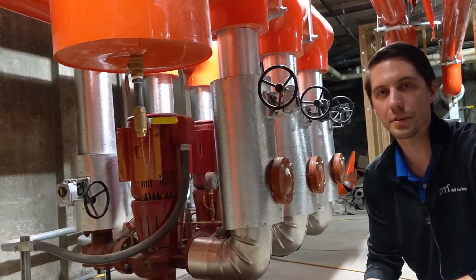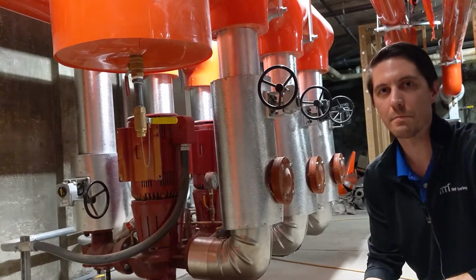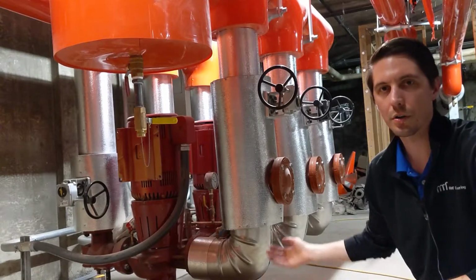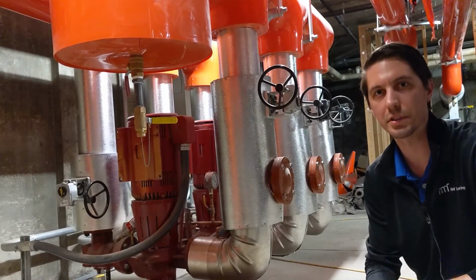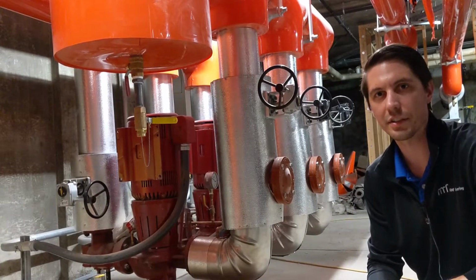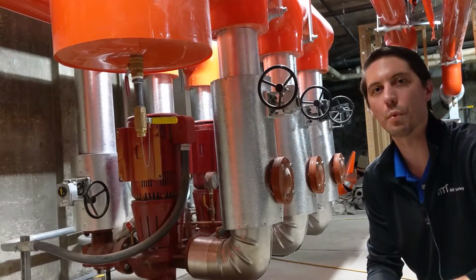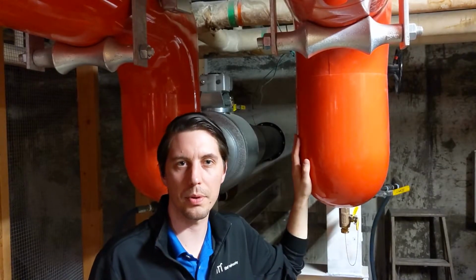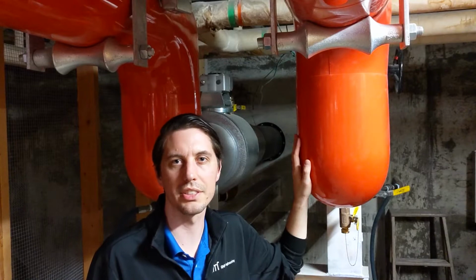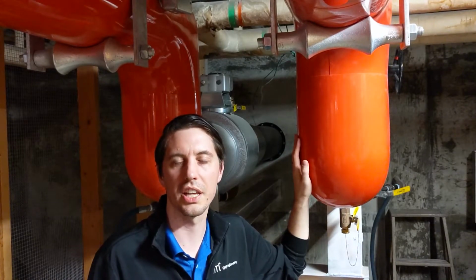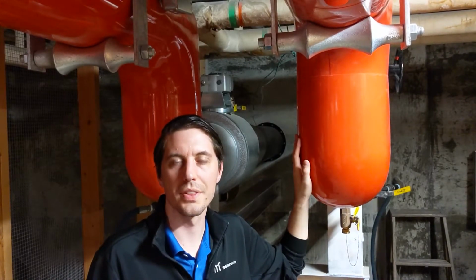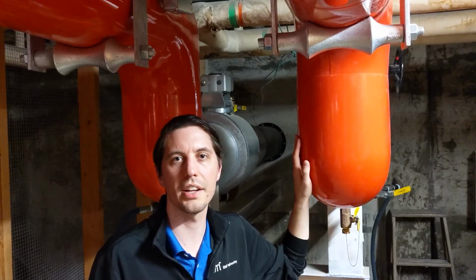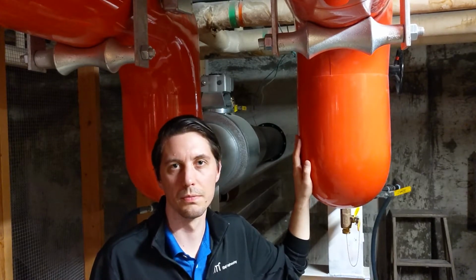Hot water is returned from the building loop and is pumped via 3 vertical inline pumps on variable frequency drives through the hot water heat exchangers, which is then distributed to the building loop and the buildings on the loop at 180 degrees. Why 180 degree hot water supply? Cornell wanted to achieve a 70-degree temperature differential to keep a reasonable pipe size. For this size of development, 180-degree hot water supply was ideal.